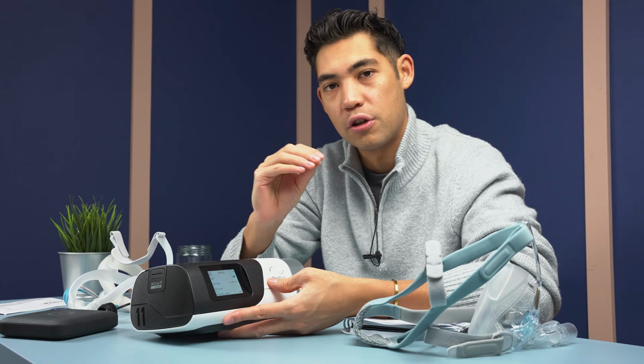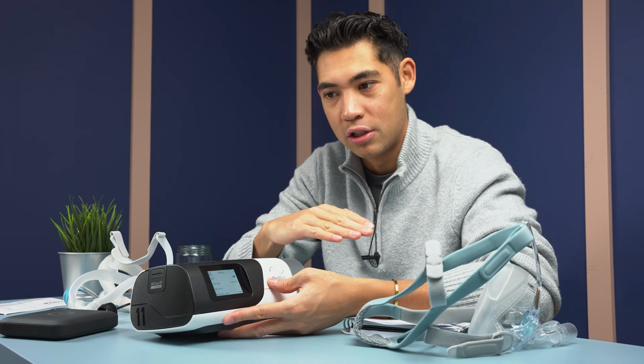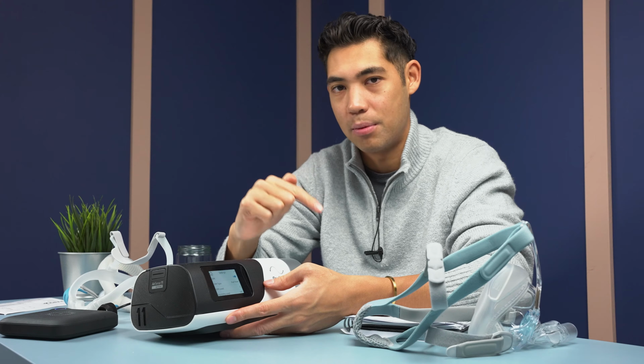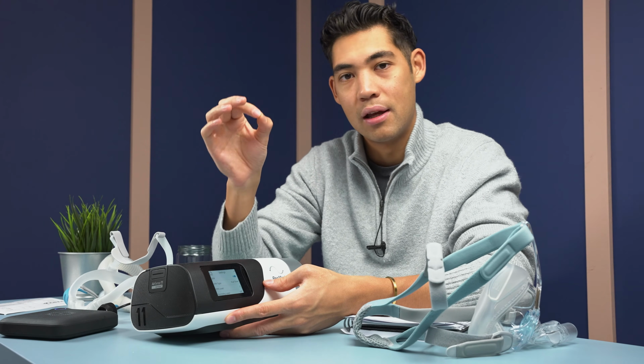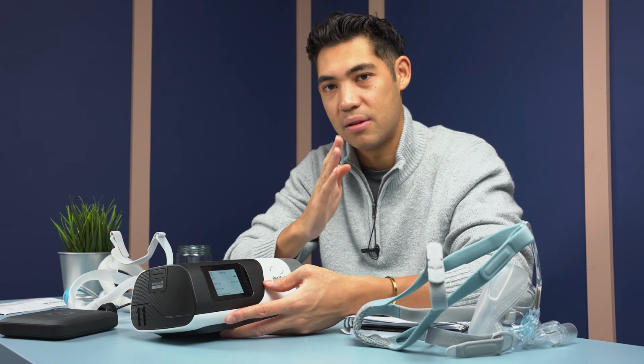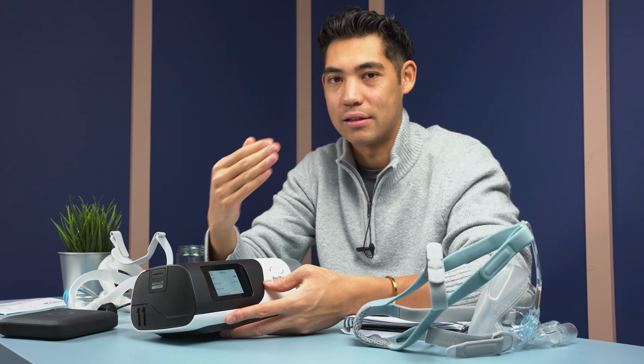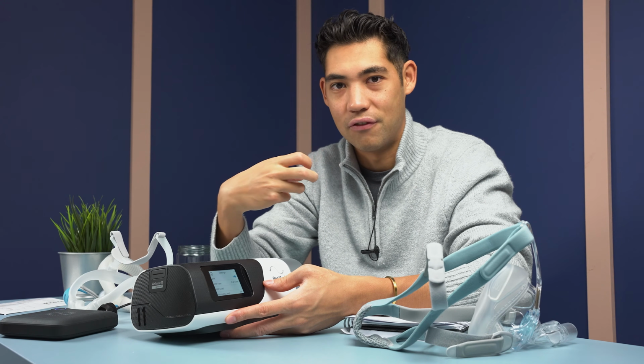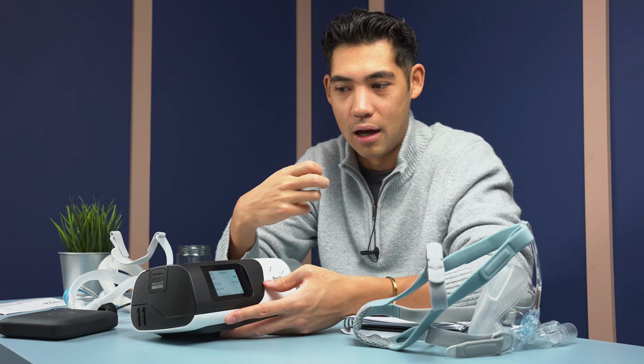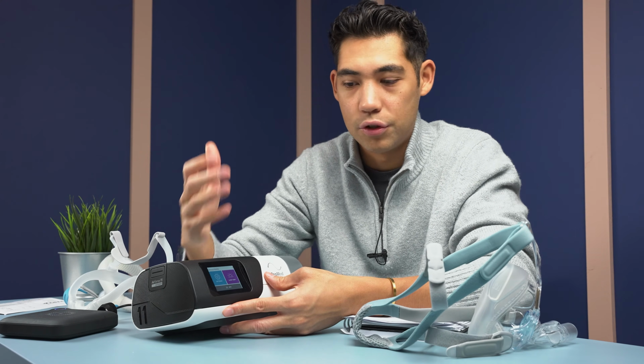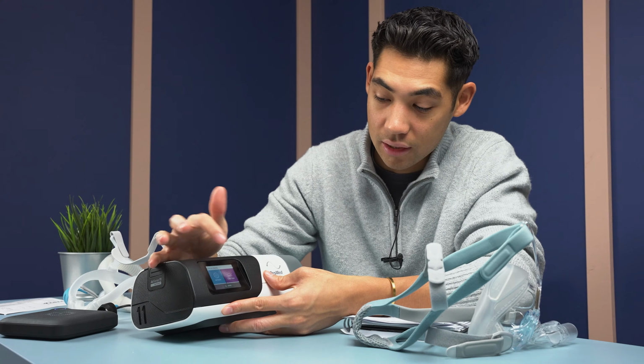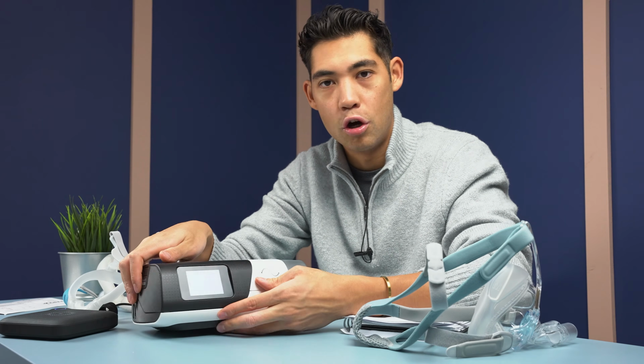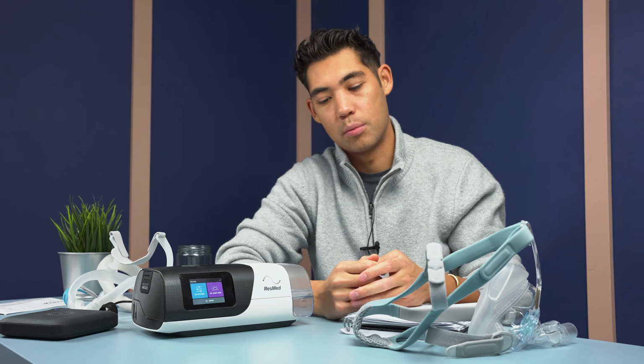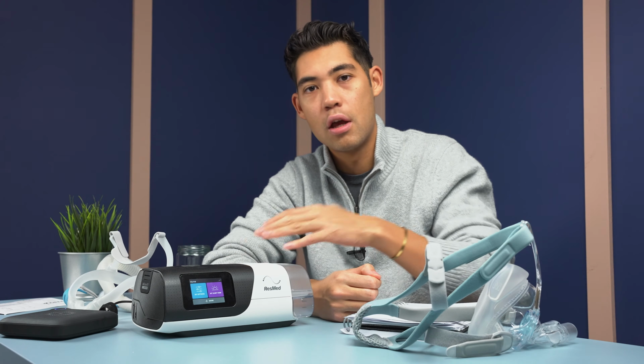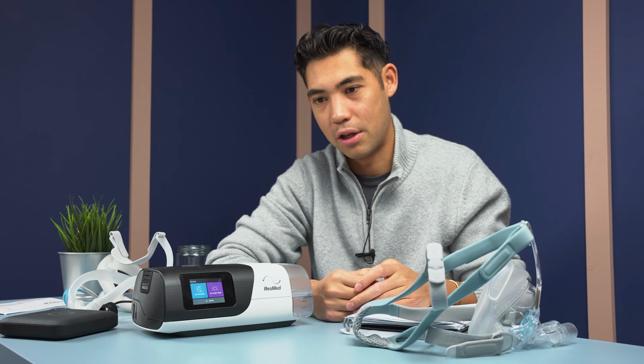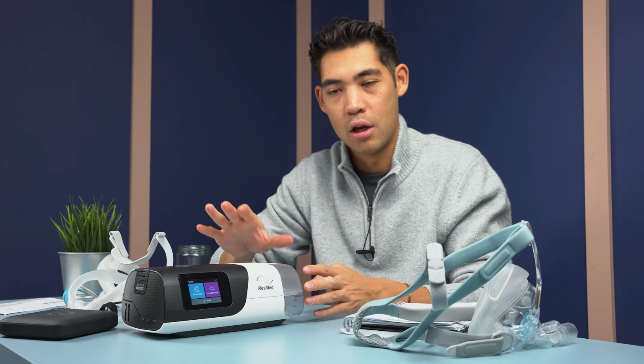Okay, now if you're at a pressure of 4, it's not gonna dip below. So it actually might be more comfortable if you step up to a 5 or 6 and you turn your EPR pressure on, so that there's just some variance between your inhales and your exhales. If you don't have that variance, it's gonna feel a lot more claustrophobic breathing with your CPAP for the first time. Now, when you're done with your pressure relief settings, you just exit the clinical menu, and then you're back to the home and you can start your CPAP therapy as per normal. Now, even though I showed you how to get to the clinical menu, make sure that you're talking to your doctor or sleep therapist before you make any changes on your machine.